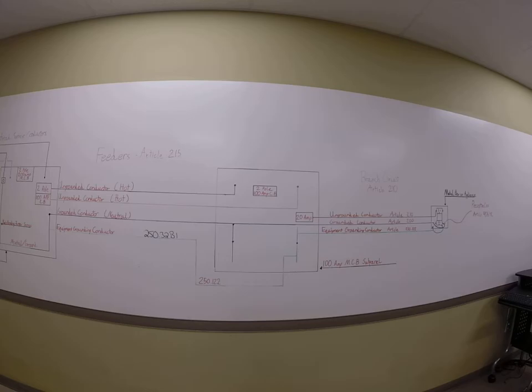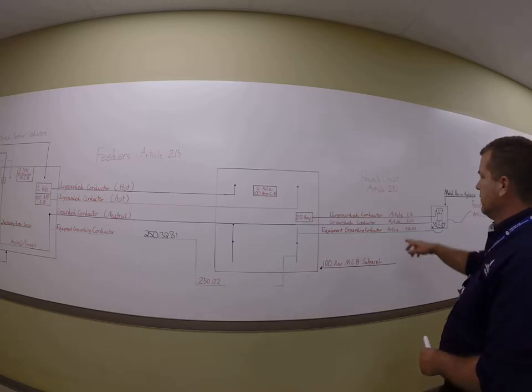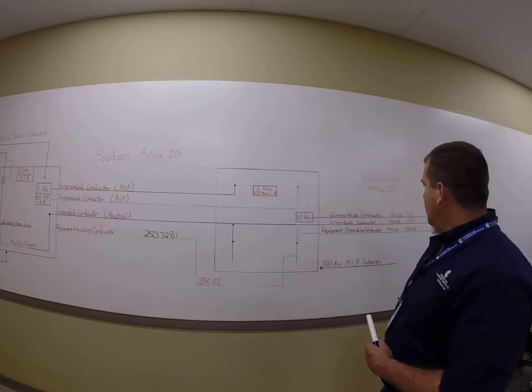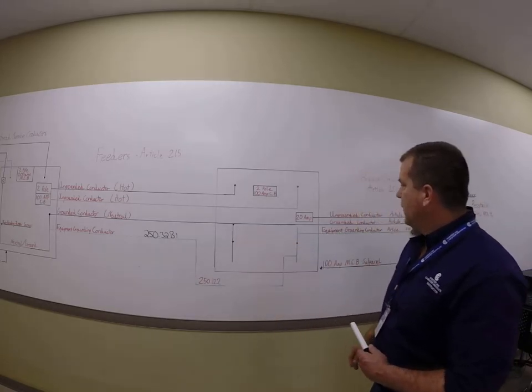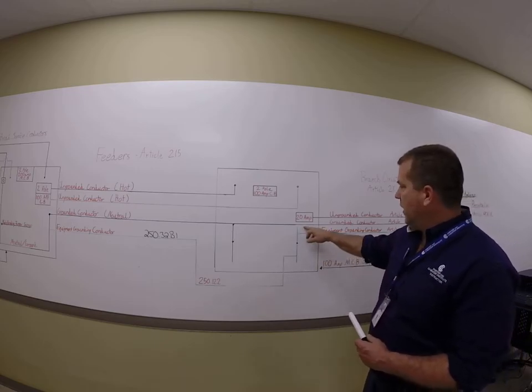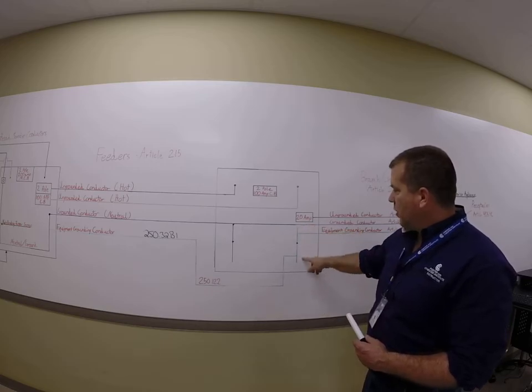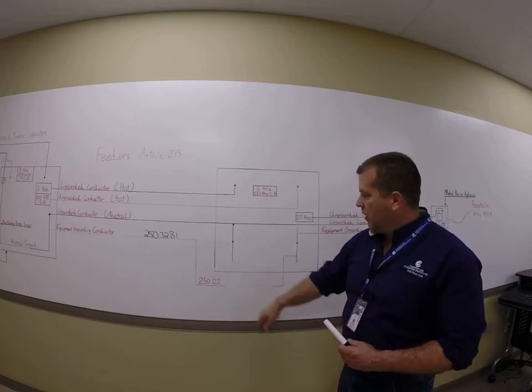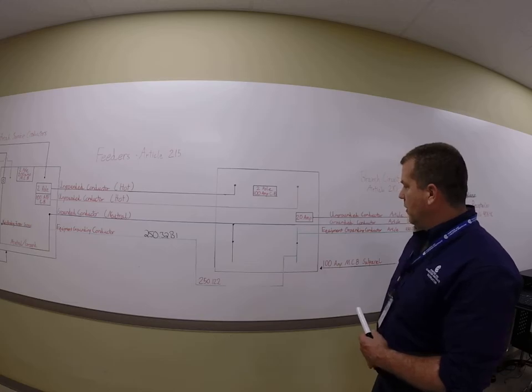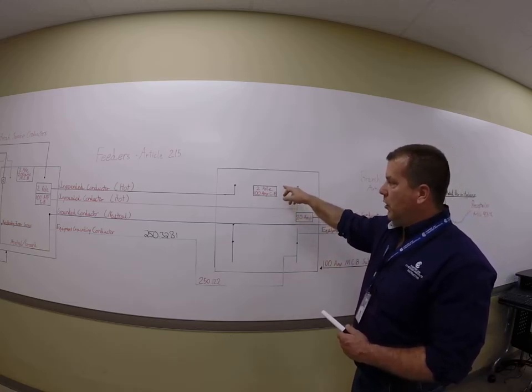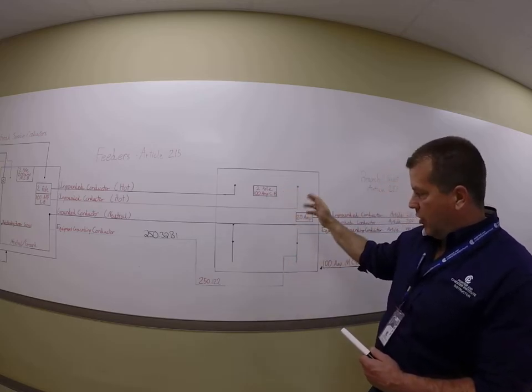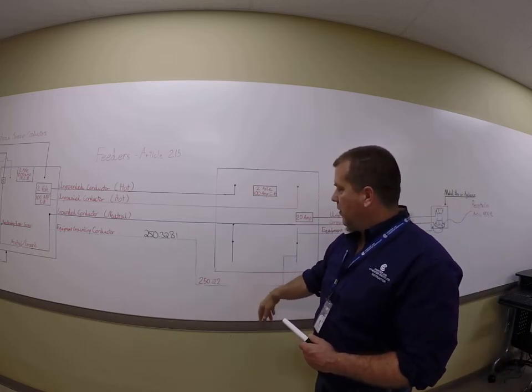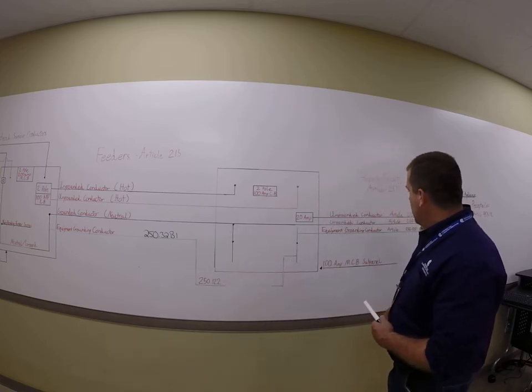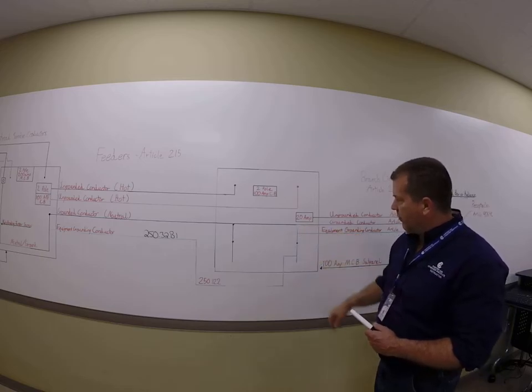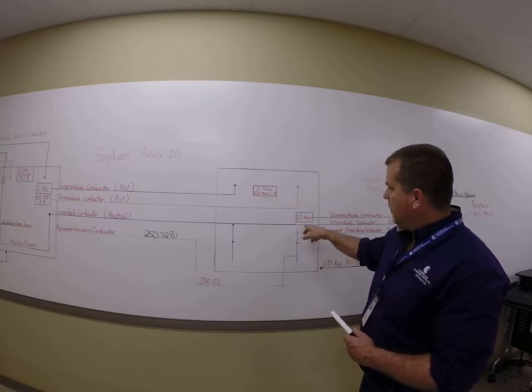So, in the other panel, we're going to notice something different than what's in this panel. So if I zoom in over here, as best I can, I want you to take a look at that the grounded circuit conductor, which is your neutral, is here. And just as an example, it's connected to a neutral bar. Your equipment grounding conductor is isolated. It's not touching your neutral bar. It's got its own equipment grounding bar, and then you have whatever size equipment grounding conductor would be required for a 100 amp service. And you would size that based on your overcurrent device. So you go to look at your overcurrent device. If you wanted 100 amp, you'd go to table 250.122 in your code book. You'd see based on 100 amp, you'd come up with your wire size. In this case, the important thing to notice here is there's no main bonding jumper. There's no connection between your equipment grounding conductor and your grounded circuit conductor.